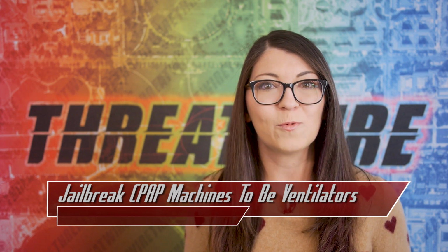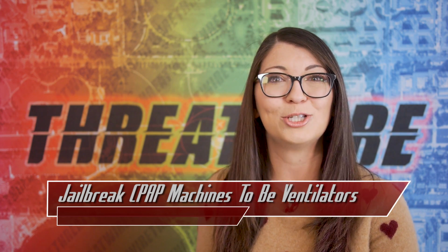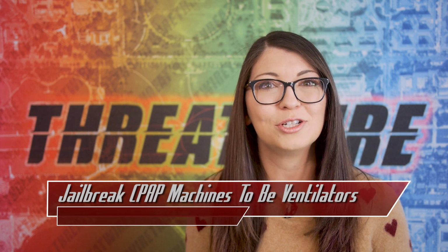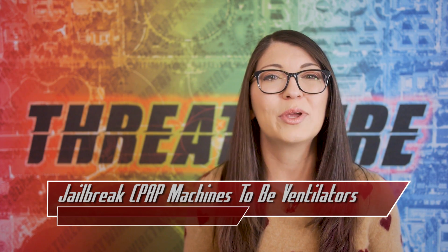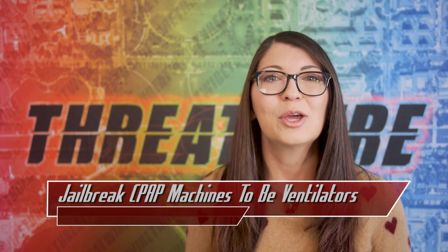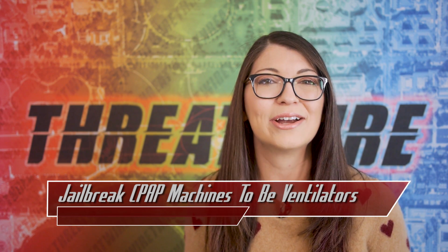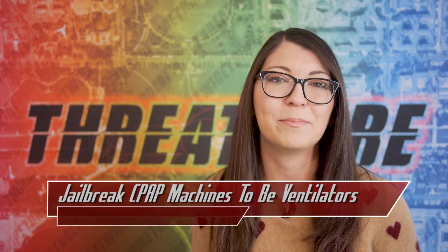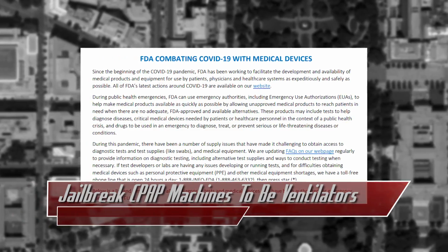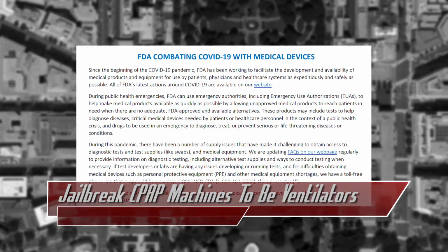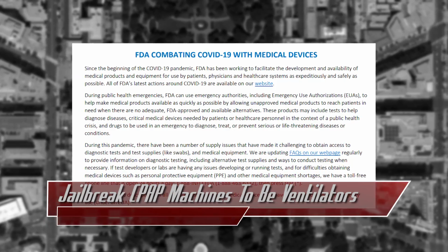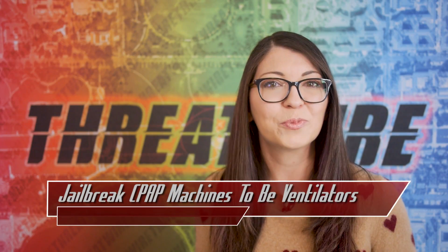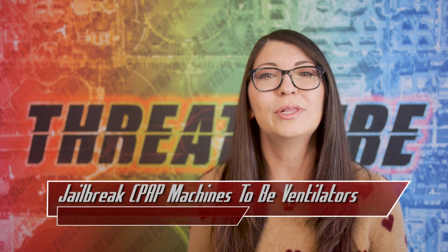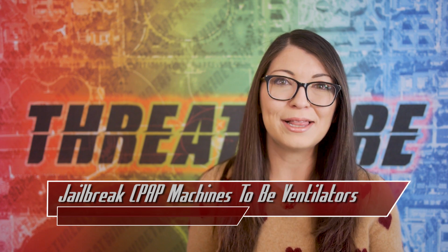Hudson found that the firmware within the AirSense 10 CPAP machine already has ventilator functions as part of its code, so he reverse engineered the device, going so far as to take it apart and turn it into a BiPAP machine. Now, CPAP machines funnel air into a mask, but more advanced BiPAP machines funnel air into the mask, then reduce pressure to a lower level to allow it back out, hence bi-level.